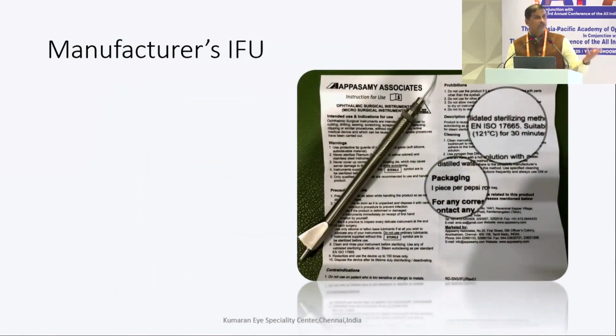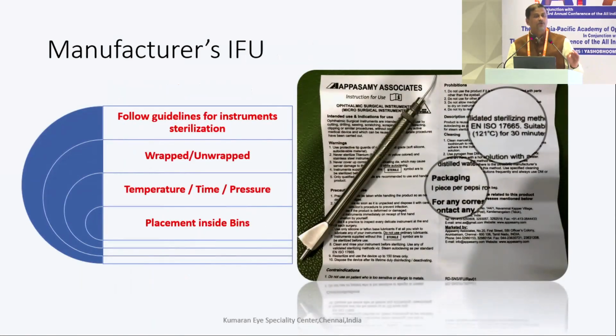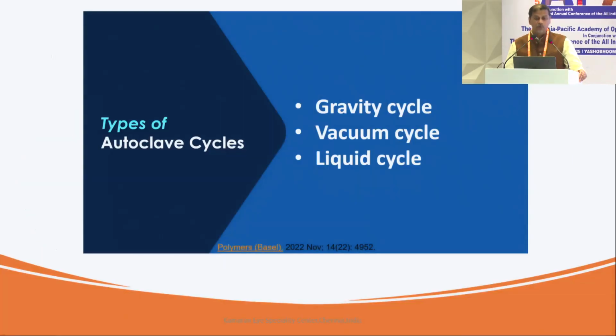As Dr. Nirmal told you frequently, always follow the manufacturer guidelines when you sterilize the goods, because when you buy a new instrument and it doesn't work after a few autoclaves, you would definitely see the manufacturer telling you that this is not the right way of sterilizing. As you could see, for the simple irrigation aspiration tubing, they have clearly mentioned how it should be packed, how it should be sterilized, and what temperature has to be used. So once you do not follow this, it's going to be difficult for you to claim your warranty also.